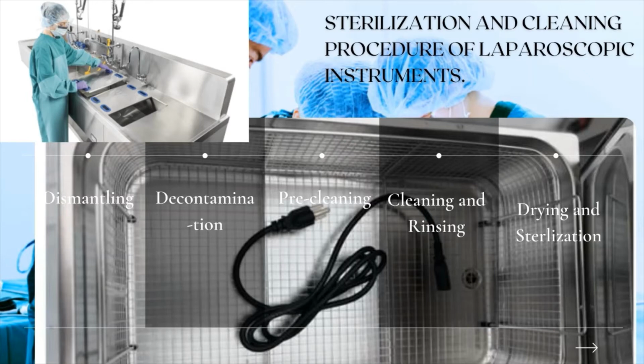There are some processes needed to clean the laparoscopic instruments. They are dismantling, decontamination, pre-cleaning, cleaning and rinsing, drying and sterilization. Dismantling. Dismantling is based on the design of the laparoscopic instruments. Dismantling varies. Decontamination. It is a process used to reduce bioburden on reusable medical devices. The process begins with removing or wiping of blood, tissue and body fluids from the instruments with the help of a sterile sponge. After this, all contaminated instruments are placed in a container containing a disinfectant solution such as 0.5% chlorine, allowing them to soak for about 10 minutes. The instruments are not left for more than 10 minutes because they get damaged.